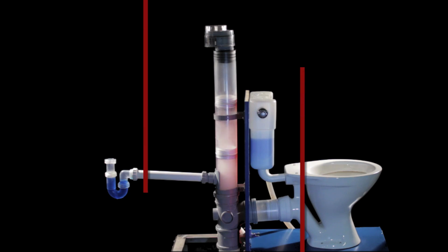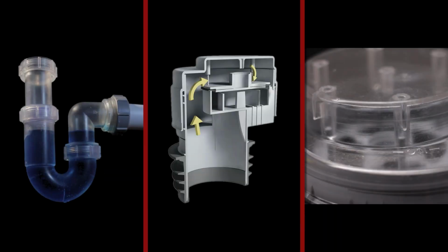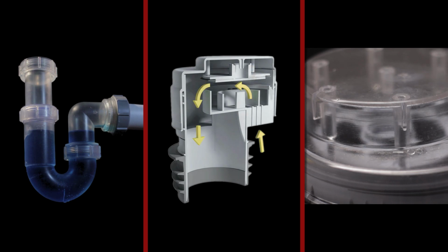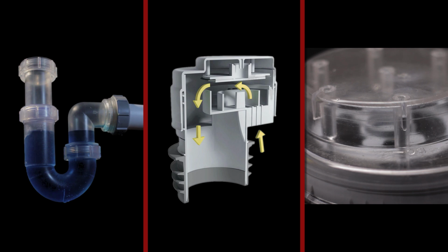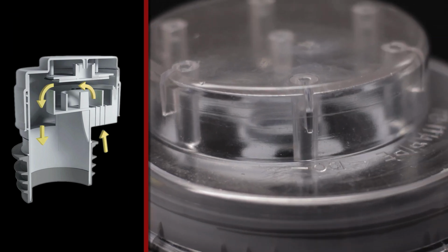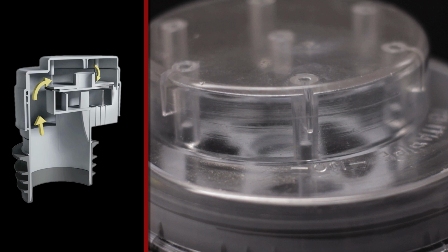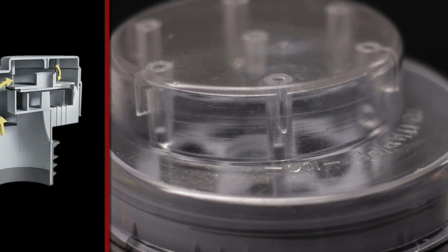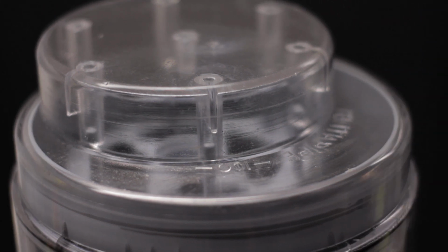The AAV houses a moving diaphragm. The diaphragm stays closed under neutral and positive pressure. During a discharge, the negative pressure within the piping system lifts the diaphragm to allow air into the system. The internal and external pressures then equalize and the diaphragm closes by gravity. The diaphragm will remain closed during positive and neutral pressure, which will keep foul air within the system.